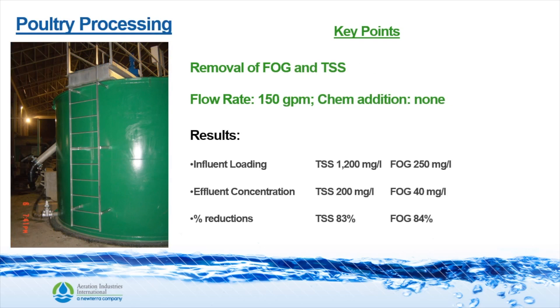In this example, we have a poultry processing plant trying to remove FOG and TSS. The flow rate was 150 gallons per minute and they were adding no chemicals. The influent loading was 1,200 mg/L of TSS and 250 mg/L of FOG. The effluent concentrations leaving the unit were 200 mg/L of TSS and 40 mg/L of FOG, yielding a reduction of 83% in TSS and 84% in FOG.